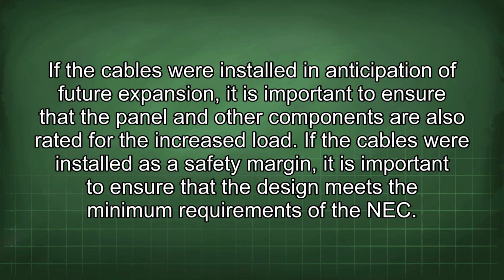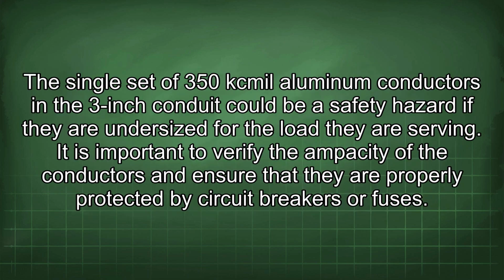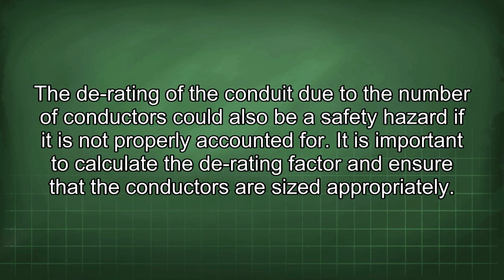If the cables were installed in anticipation of future expansion, it is important to ensure that the panel and other components are also rated for the increased load. If the cables were installed as a safety margin, it is important to ensure that the design meets the minimum requirements of the NEC. The single set of 350 kcmil aluminum conductors in the 3-inch conduit could be a safety hazard if they are undersized for the load they are serving. It is important to verify the ampacity of the conductors and ensure that they are properly protected by circuit breakers or fuses. The derating of the conduit due to the number of conductors could also be a safety hazard if it is not properly accounted for. It is important to calculate the derating factor and ensure that the conductors are sized appropriately.